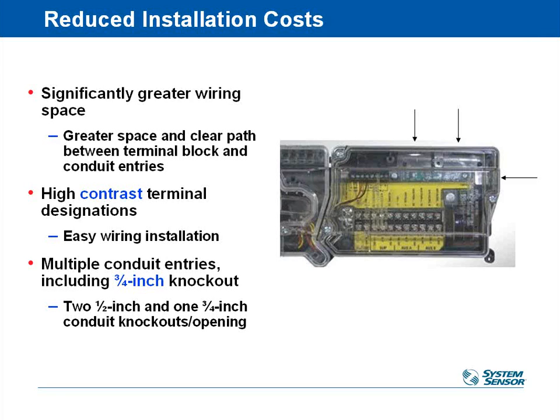All right, so this is the right half side of that two-piece design of those detectors. The left side is the detector head itself. The right side is the control wiring. There are 3 different places you can bring conduit in, the top or the side. You can bring power in and control out of a separate one. And there are 3/4 inch conduit knockouts.